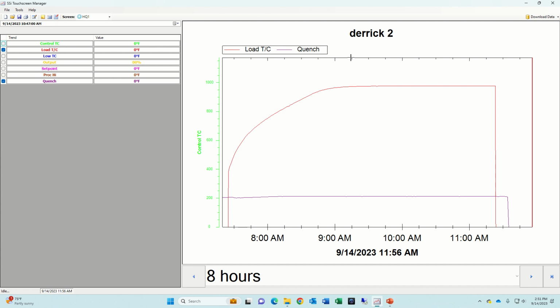So that means that with this chart, you do have to print a separate cover page to include all the customer information, customer name, the PO number, the lot number, the work order number, and maybe even the soak start and soak stop time, because we can't do it on this chart. This is simply time and temperature with each pen. It's all we can do. Okay, not the best, but it's better than nothing.